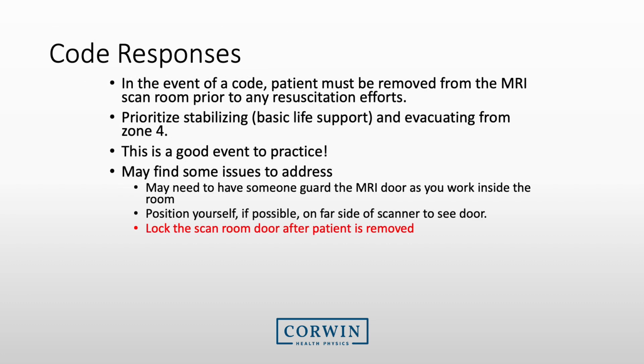Each facility needs to know what they will do for a code response. Your standard practice should be to remove the patient from the room prior to any resuscitation efforts. We recommend you practice this event with your code team so they know not to enter the MRI room. Once you have brought the patient out, you may need to guard or lock the MRI room door to prevent individuals from entering it.